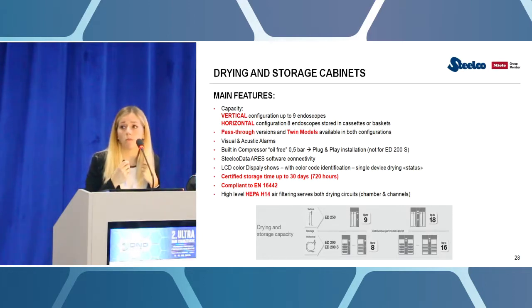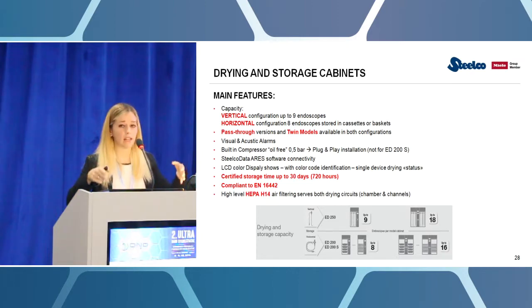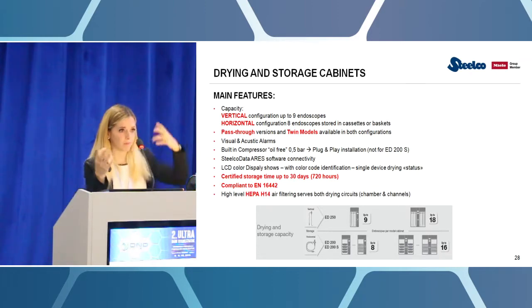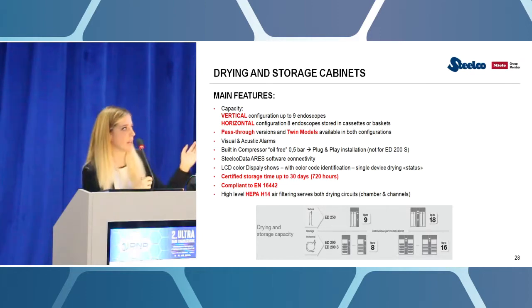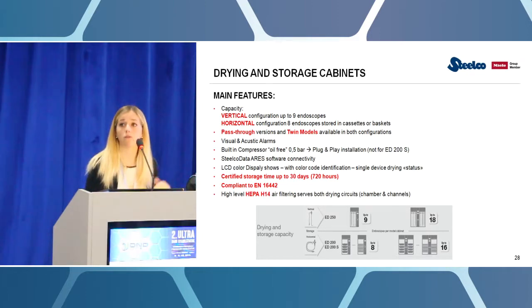You're touching the endoscope less, because you have separated levels, one from the other. You simply put the endoscope inside the tray and you load that into the drying cabinet without touching and manipulating it to be able to hang it into the supports of the vertical cabinet.